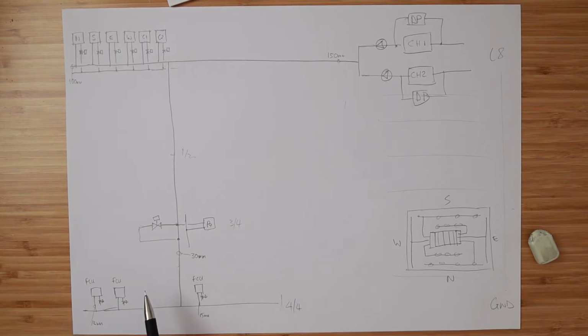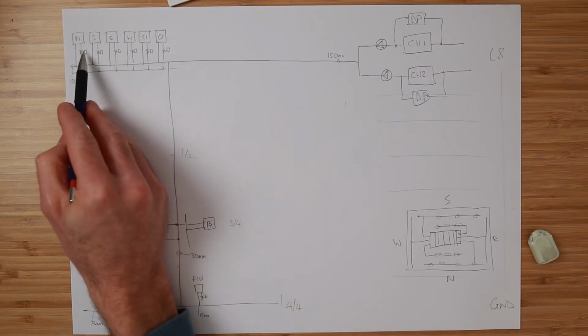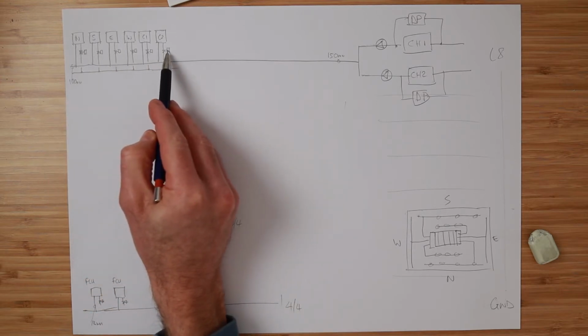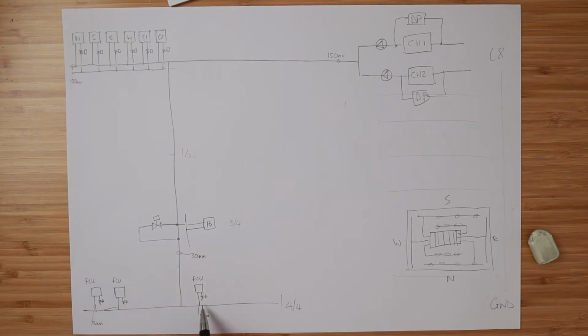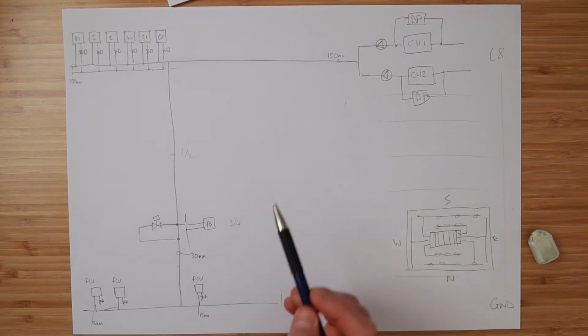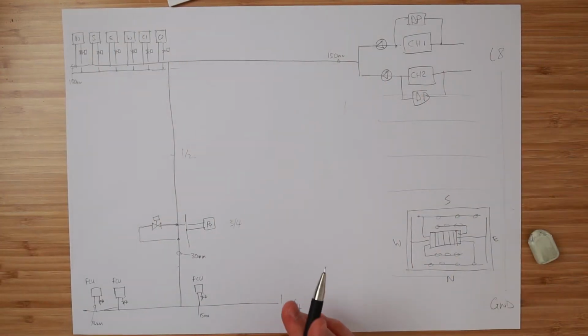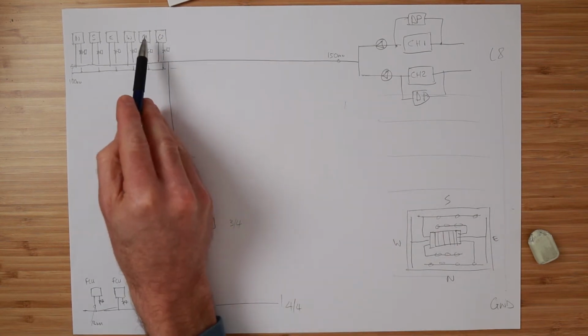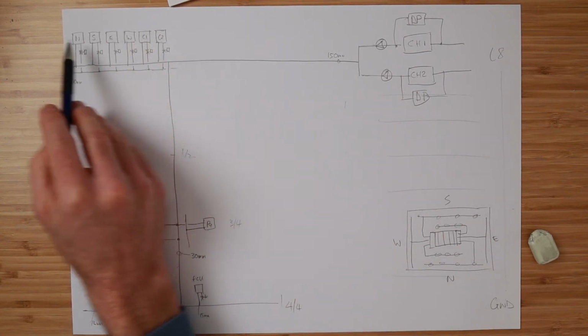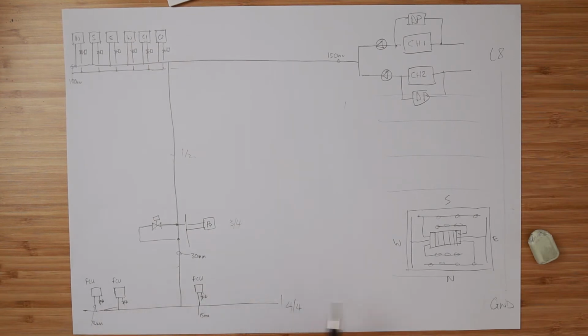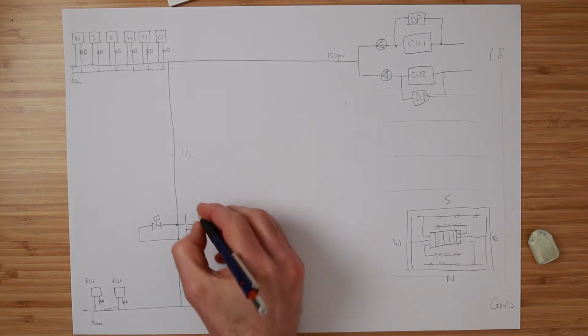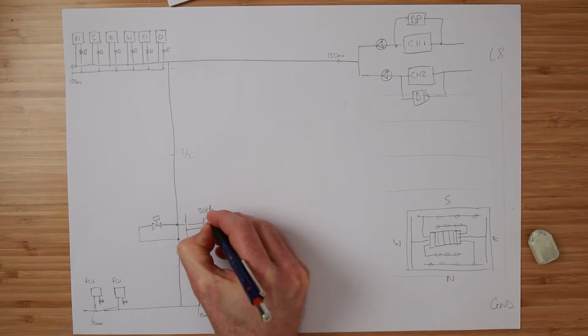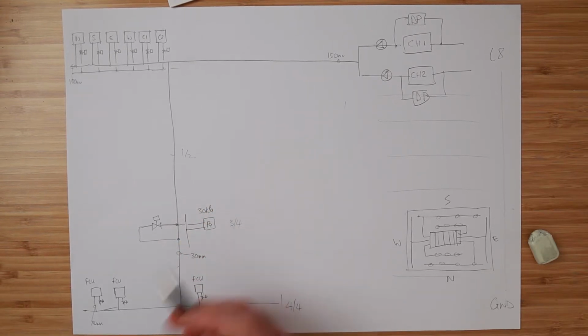So when they did the chill water system balance, and they opened up all these valves, the VMS valves fully open, the control valves, and these 3 fan coil valves fully open, and they set the pump to the design speed, so the design volume of water through here, and the whole thing was balanced and perfect, with the correct design flow rates through each coil, a bit more here, a bit less there, with the correct design flow rates through our fan coils. The whole system was perfectly balanced. At that point in time, maybe we had 30 kPa down here. 30 kPa. So 30 kPa becomes your set point for your pressure control.